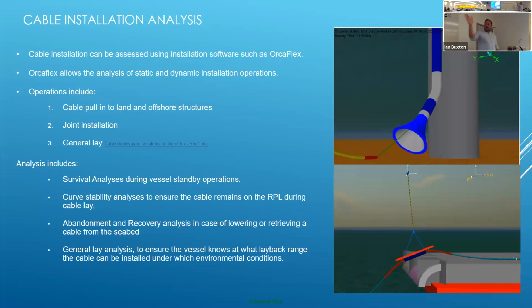We look at curve stability analysis to ensure the cable remains on the route position listing during cable lay. So in an ideal world, I could lay from A to B, so our landing point to our offshore substation would be a complete straight line. That's not the reality. We have to lay radiuses. So when you're laying a radius with a cable, if you've got a smooth seabed, how do you guarantee that radius isn't going to be pulled out when you're going around the corner? And that's where we look at the stability to make sure it stays in place. So the tension it's exposed to on that radius by the vessel induced tension doesn't allow that radius to be pulled out and end up with a cable that's too tight and goes in a straight line.